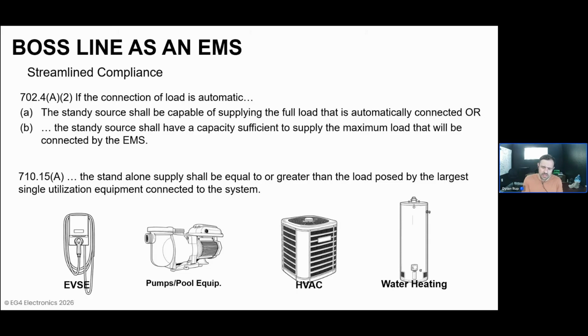a standalone system shall be equal to or greater than the load posed by the single largest load on site. And that makes a lot of sense. It essentially says, don't connect a load that draws more power than what your power source is able to deliver. Now, for a lot of systems, again, this means we're going to have to relocate a ton of loads to pull those out of the non-backed up panel and now create a new backed up panel.